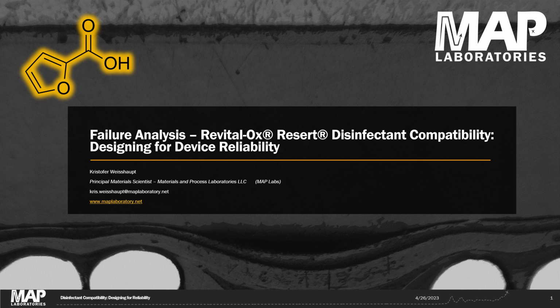Today I'm going to talk about an electrical leakage failure in a medical endoscope, how we were able to determine the root cause of the electrical leakage, the tools we have at our disposal for determining what types of chemicals devices were exposed to, and the component level tests we can use to design for better device chemical compatibility and reliability. The device that originally detected the electrical leakage was a Fluke ULT 800 electrical leakage test kit.